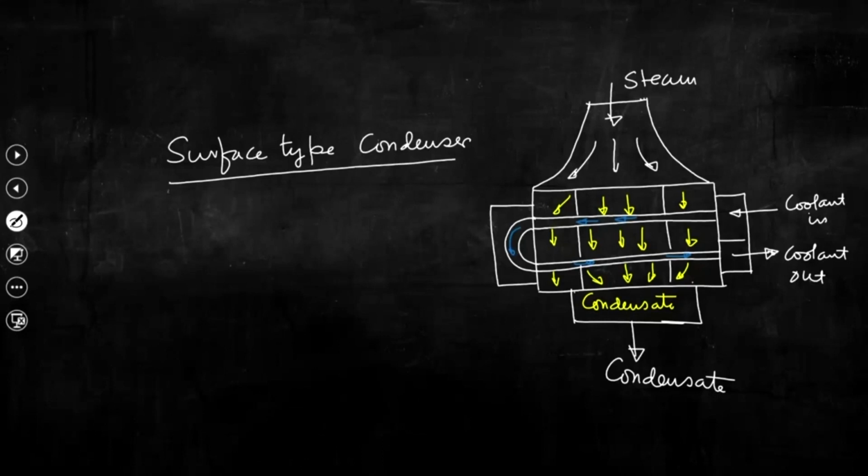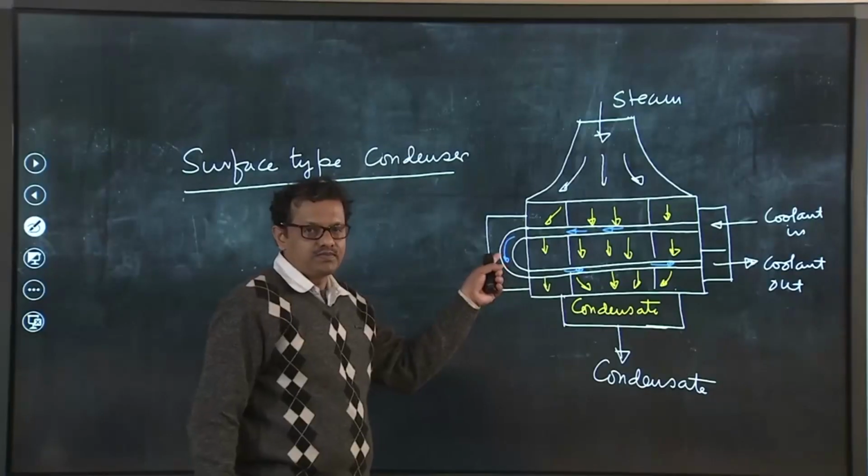Now, it is not mandatory that always condenser will be two pass condenser, but single pass condenser is also fine. In case of a single pass condenser, this tube will be having one inlet and one outlet. So, tubes are not connected by using this bent tube.